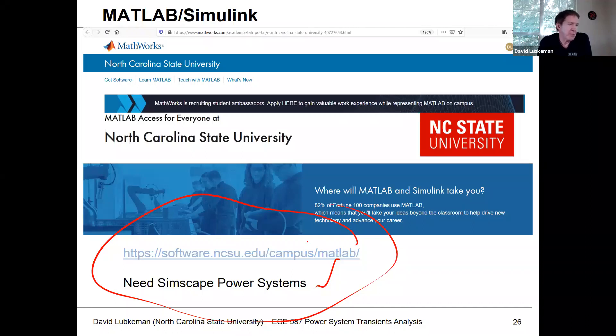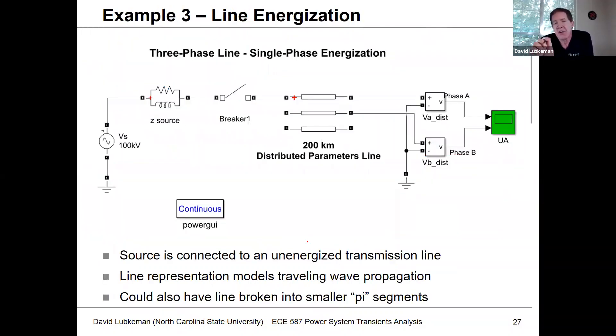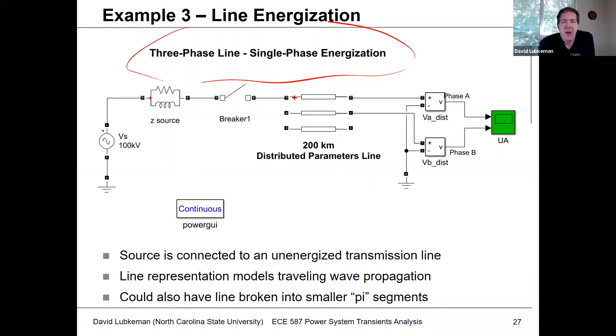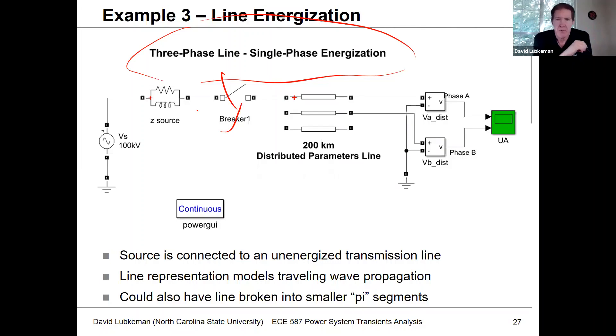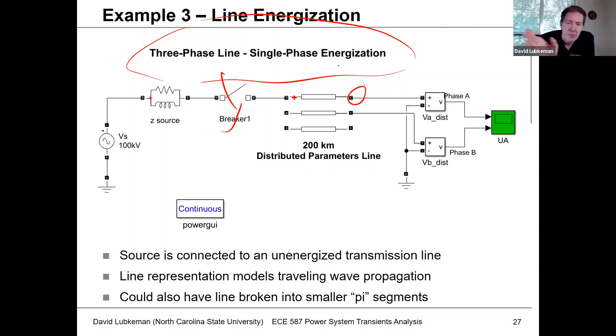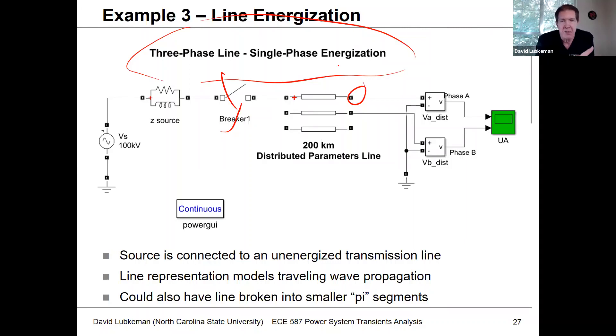The reactance-to-resistance ratio determines the slope and the peak value of the current. Another scenario requiring different modeling is line energization. If you have a three-phase line and you energize a single phase, closing the switch sends a square-wave pulse down the line. When it hits a discontinuity, there's reflection, and the pulse bounces back and forth — creating a transient. This is a very common scenario on transmission systems and also happens on distribution circuits, though the impacts are more felt at the transmission level.